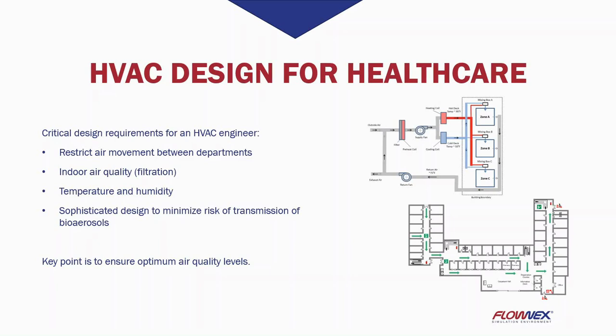The indoor air quality together with temperature and humidity are also important factors. Finally, the sophistication of the design to minimize transmission, which involves the designation of different types of rooms with different pressure and flow requirements. An interesting fact is that airborne transmission accounts for approximately 10% of all nosocomial infections, that is, infections that originate in a hospital.